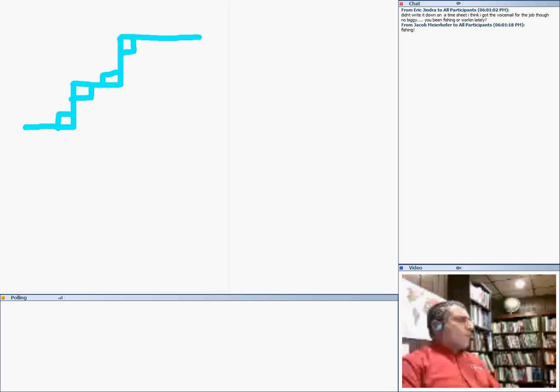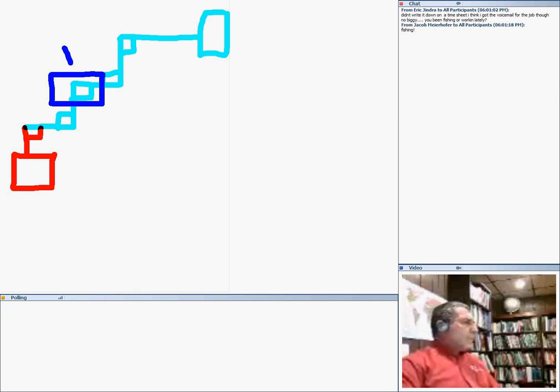See, if I want to go from this panel right through, I don't want any 90s. You just go right through the panel. So there's no, I need to add one more. I add one more here to get down to this panel, right? Now I exceeded this angle; here I will be exceeding the 360 degrees. So don't worry. What do you do? You go somewhere in here and you put yourself a J box, or a pull box, as a matter of fact, depending on the conductor. A pull box or a J box, depending on the size of the conductor.